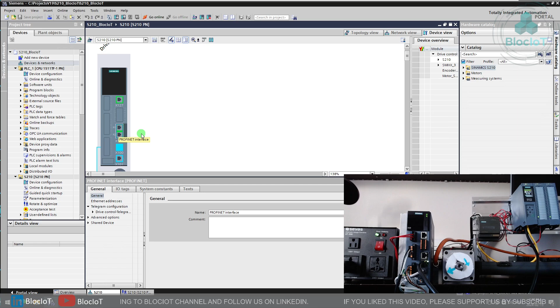Let's just go to the drive and then select the Profinet port. Under the telegram configuration, select the device control telegrams, and make sure Telegram 105 is selected. In general, a telegram is just a standard way to communicate between a Siemens drive and the PLC, and each telegram has its own meaning and you can use them for different purposes. For example, for this demo, Telegram 105 has all the information that we need, so we'll just leave it as the default.